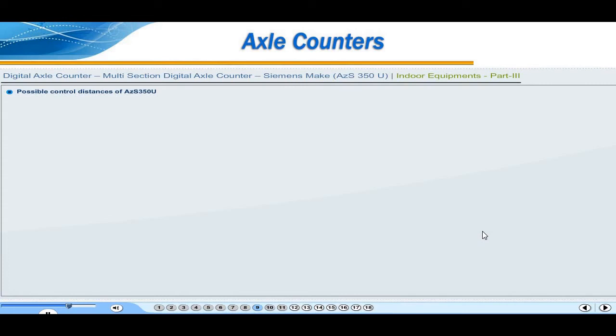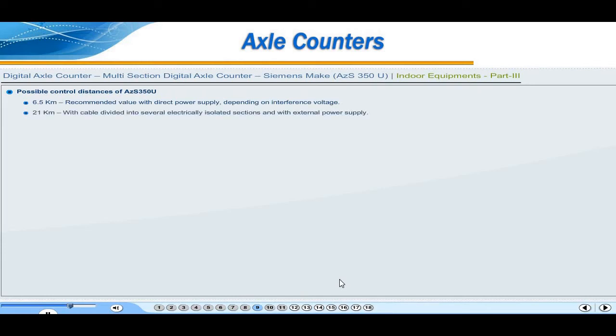Possible control distances of AZS350U: 6.5 kilometers, recommended value with direct power supply depending on interference voltage. 21 kilometers, with cable divided into several electrically isolated sections and with external power supply. Restriction by the following parameters: cable capacitance less than or equal to 325 nanofarad, that is approximately 50 nanofarad per kilometer, with electrically continuous telecommunications lines.